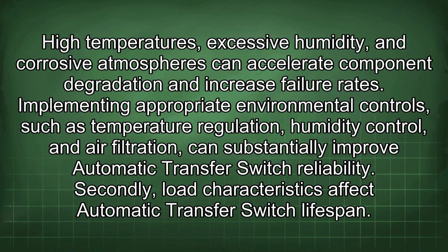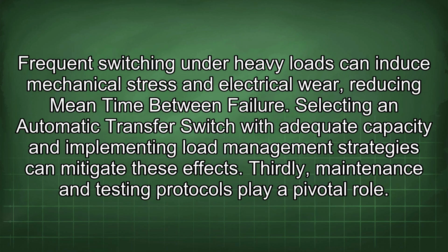Secondly, load characteristics affect automatic transfer switch lifespan. Frequent switching under heavy loads can induce mechanical stress and electrical wear, reducing mean time between failure. Selecting an automatic transfer switch with adequate capacity and implementing load management strategies can mitigate these effects.